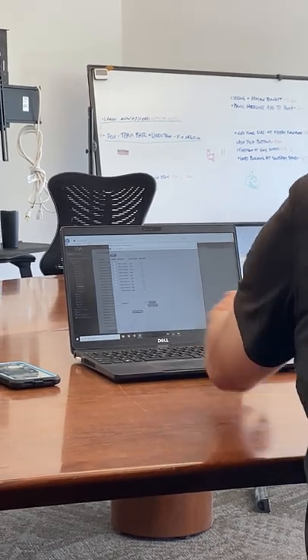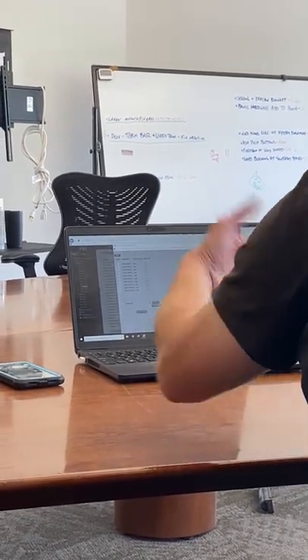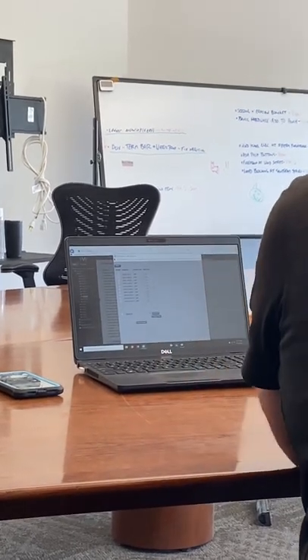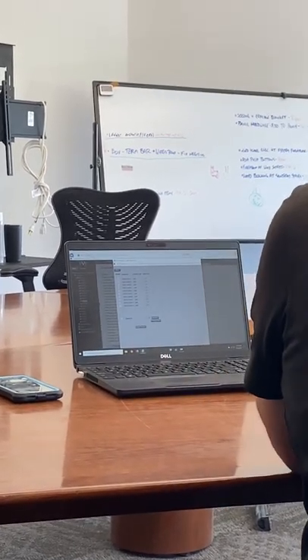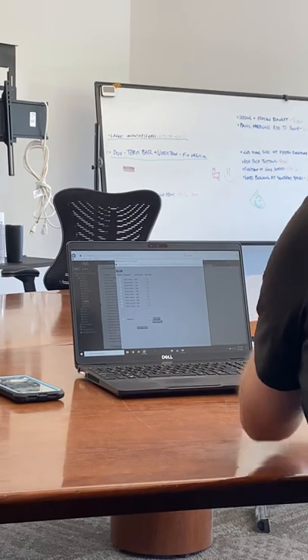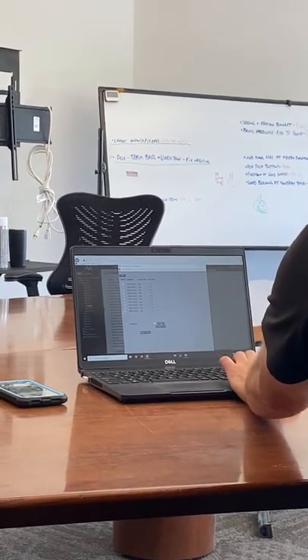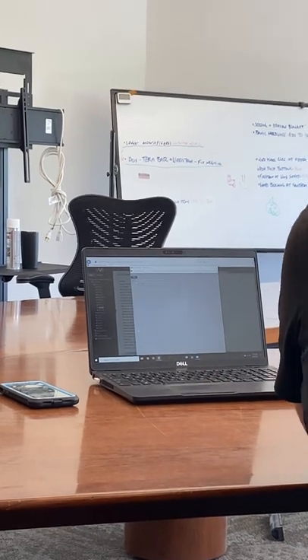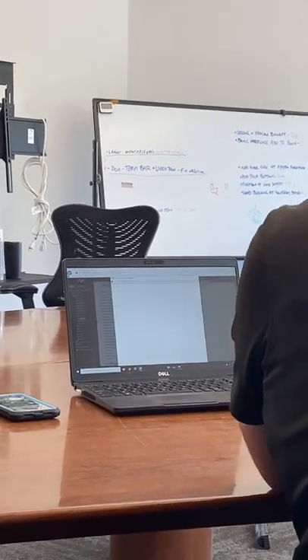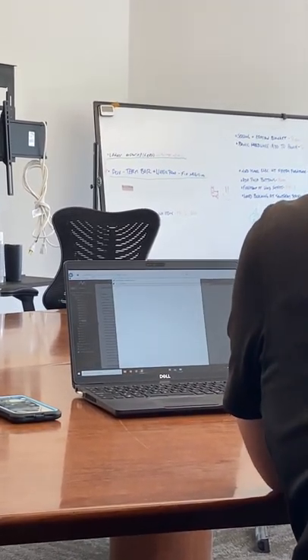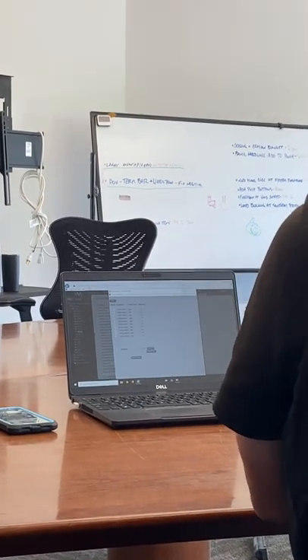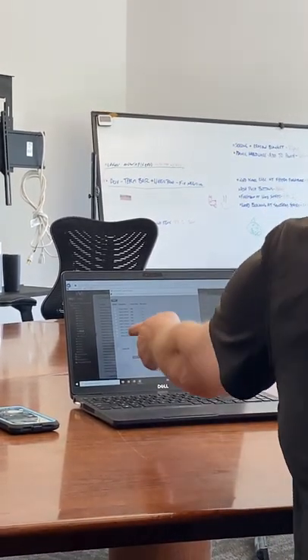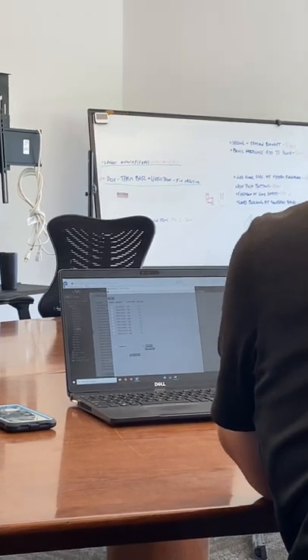And then here it pulls up everything — all the available rooftops that are all the same type, obviously minus five because it's a VAV rooftop, not constant volume. We can say we want to do two degrees for all of them. We set to all, and then they all change to two, and then you can apply. So that'll send it out to all the rooftops. You can do that with room temp set point or any box you can Alt+click on to global modify it.